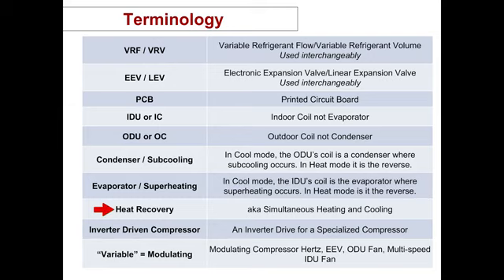Heat recovery. That's how you get simultaneous heating and cooling. We're going to go over that in a section. And then the variable aspect equals modulating. You can see the modulating compressor. An EEV is a stepper motor. It modulates. The fan is a BLDC motor, a brushless DC motor. And you could have a multi-speed indoor fan.